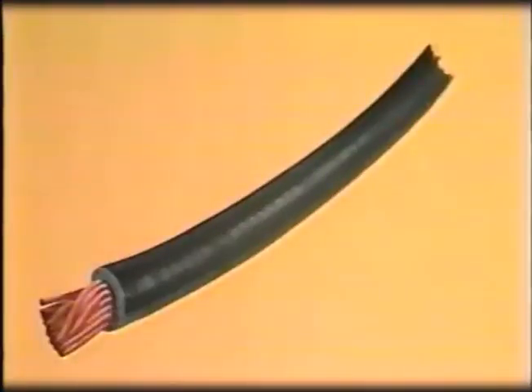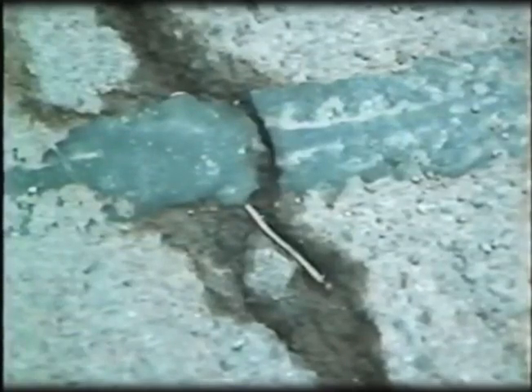This can be done by using the same instrument with the water supply disconnected. Based on the failure survey, a large percentage of failures could be prevented by using a more durable wire. Most failed loop systems studied were constructed according to a specification calling for 14-gauge stranded copper signal cable with a polyethylene insulation. This wire could not survive the stresses caused by even minor pavement disruption, such as creeping, cracking, and thermal expansion and contraction. Nor could it withstand exposure to water and debris from minor sealant failure.